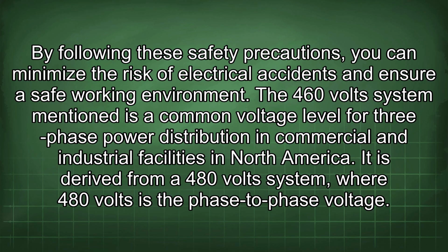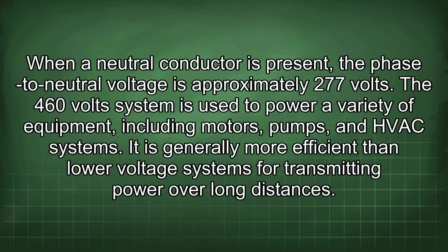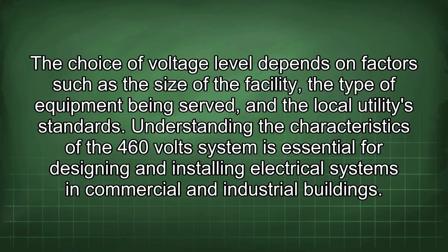The 460-volt system mentioned is a common voltage level for three-phase power distribution in commercial and industrial facilities in North America. It is derived from a 480-volt system, where 480 volts is the phase-to-phase voltage. When a neutral conductor is present, the phase-to-neutral voltage is approximately 277 volts. The 460-volt system is used to power a variety of equipment, including motors, pumps, and HVAC systems. It is generally more efficient than lower voltage systems for transmitting power over long distances. The choice of voltage level depends on factors such as the size of the facility, the type of equipment being served, and the local utility standards. Understanding the characteristics of the 460-volt system is essential for designing and installing electrical systems in commercial and industrial buildings.